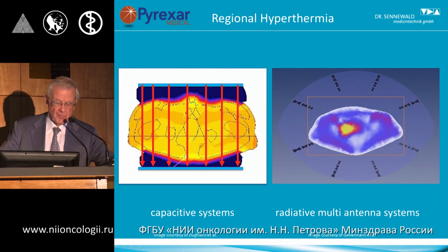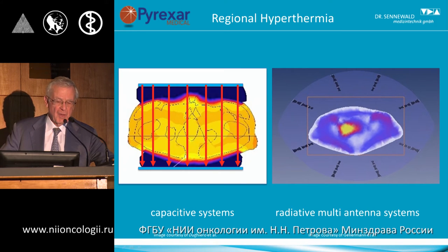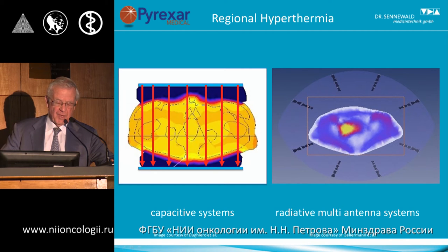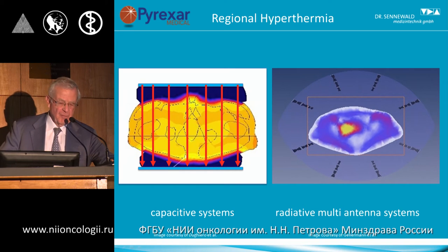In capacitive mode, the patient is placed between two electrodes and electrons travel from one plate to the other through the patient, taking the easiest path — going straight top to bottom, leading to seemingly equal heating of the entire patient cross-section with no focusing possibility.